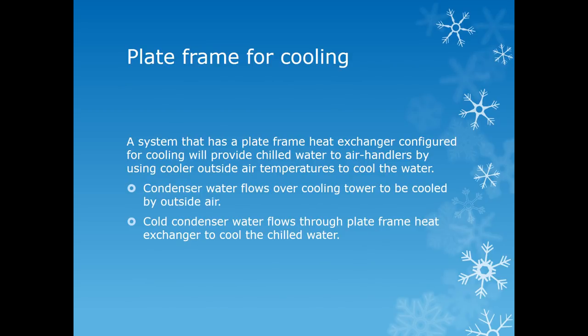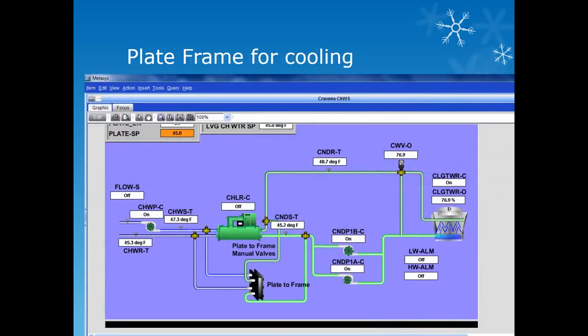This system has a plate frame heat exchanger configured for cooling. It will provide chilled water to air handlers by using cooler outside air temperature to cool the water. The condenser water flows over the cooling tower to be cooled by outside air. That water is then flowed through the heat exchanger to help cool the chilled water. This configuration is generally used during the colder months of the year and is a good source of providing cold water to the air handlers.